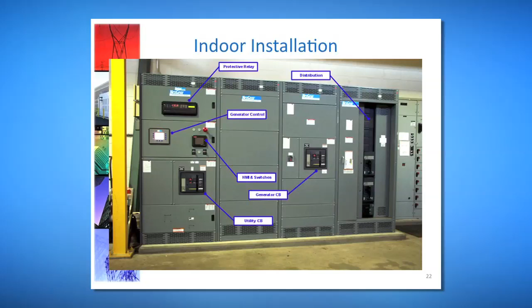Protective relaying is what the utility wants, the right brains and the right muscle, which is the circuit breakers, plus a little bit of brain for the generator. Most generators, when they come out and sit behind a building, know how to run at 60 hertz and rated voltage, but they don't know how to run in parallel with the utility. They need a brain upgrade, so we make sure we put that in, along with better control, to get the job done.